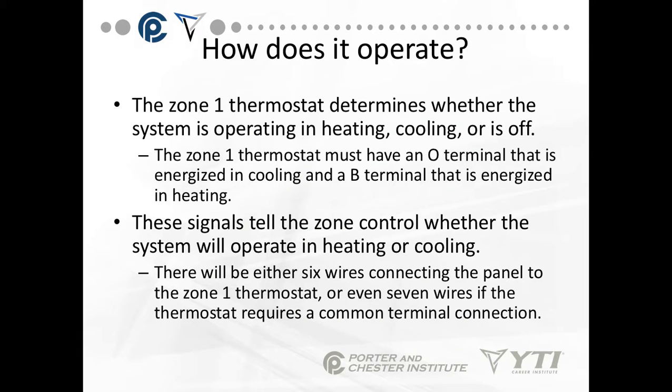How does it work? Zone 1 thermostat determines whether the system is operating in heating, cooling, or is off. The Zone 1 thermostat must have an O terminal that is energized in cooling and a B terminal that's energized in heating. The O terminal is always energized in cooling; the B terminal is energized in heating. Don't get the two confused. These signals tell the zone control whether the system will operate in heating or cooling.